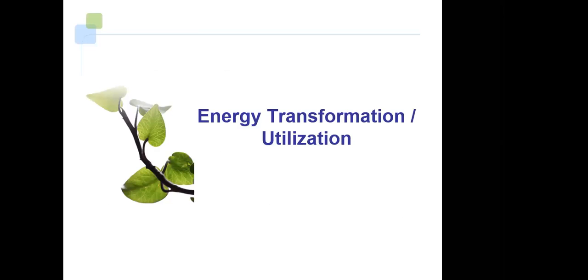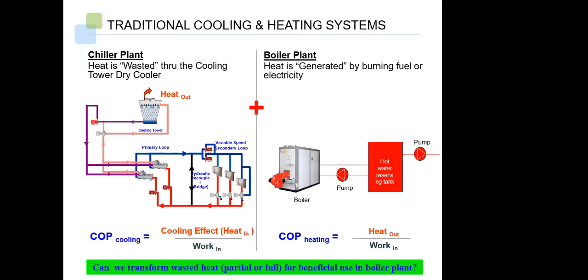So second part on the same on the plant room is that typically what happens in many of the plant rooms, typically in the hotel industry, you might find that we have chilled water plant, which is for the air conditioning of the hotel. At the same time, we have the boiler plant, which is used for the kitchen purpose, for the laundry, and for various other applications which they use for the hot water. So what they do in the chilled water plant, they pick up the heat from the indoor and they reject the heat to the atmosphere, to the cooling tower. So basically heat is wasted. Whatever heat we have picked, it is being wasted to the atmosphere by rejection.